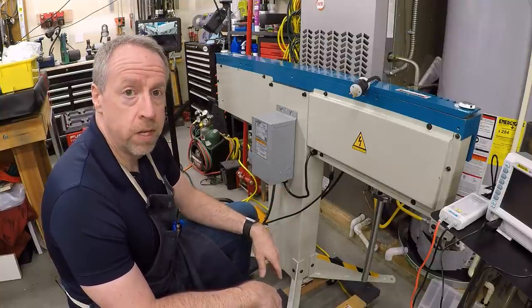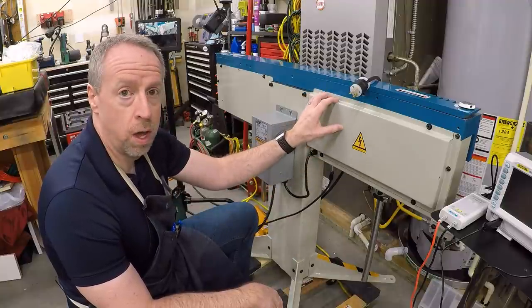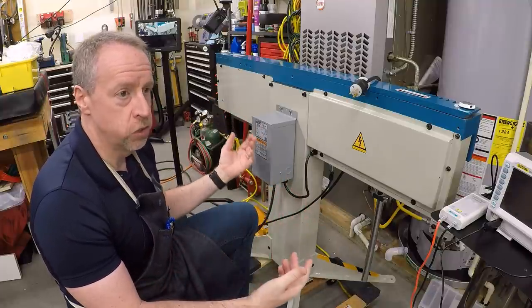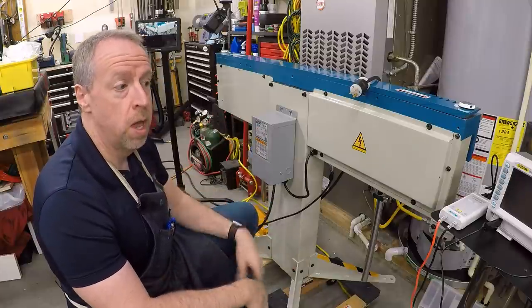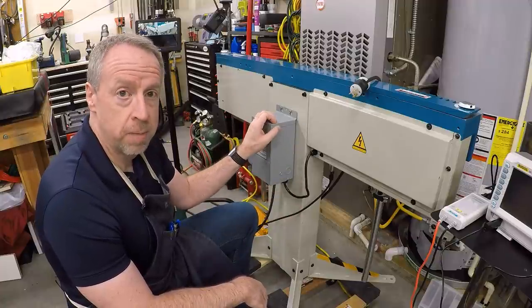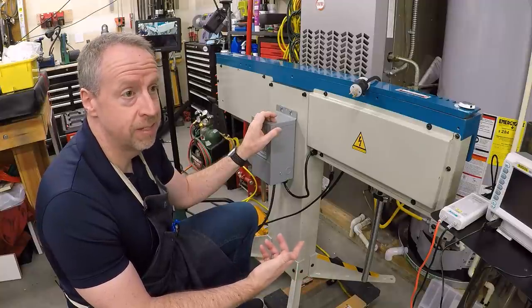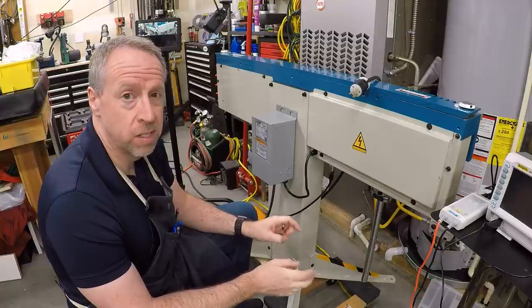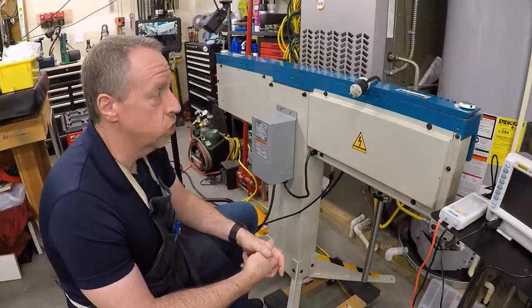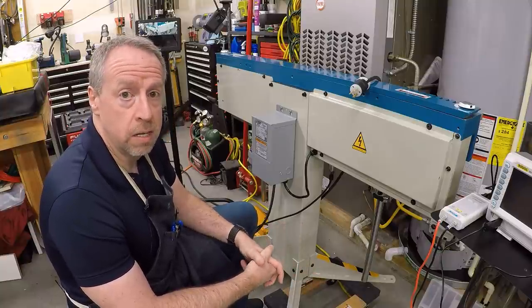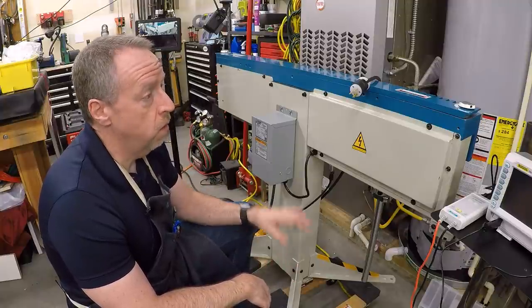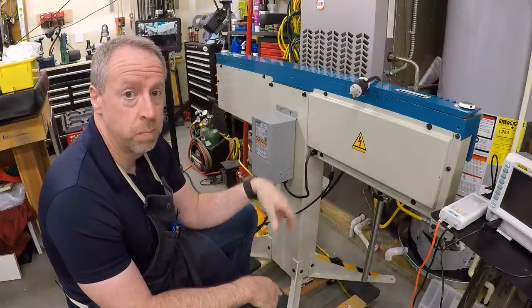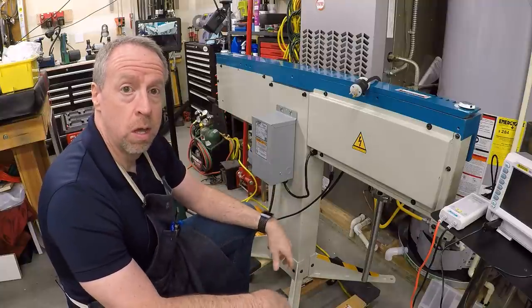The other thing you'll note from that video is that I measured the current draw of the tool, partly to make sure my transformer was in spec and could handle the load, and to illustrate current flow in a buck transformer. But it didn't turn out as expected. The nameplate says it draws 10 amps. We measured 17.5 RMS. That seems a little high. I contacted the manufacturer. They thought it seemed high, but after having me do some tests, they didn't think anything was necessarily wrong with it. But they decided to ship me some replacement parts just in case.